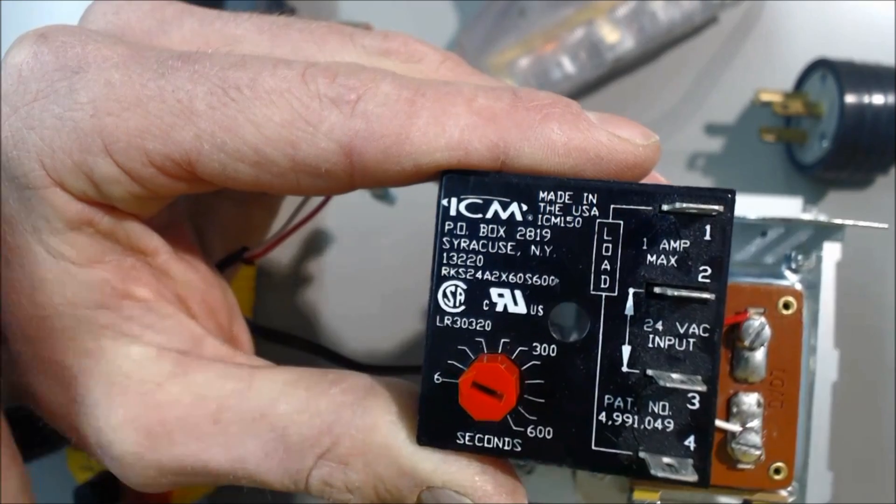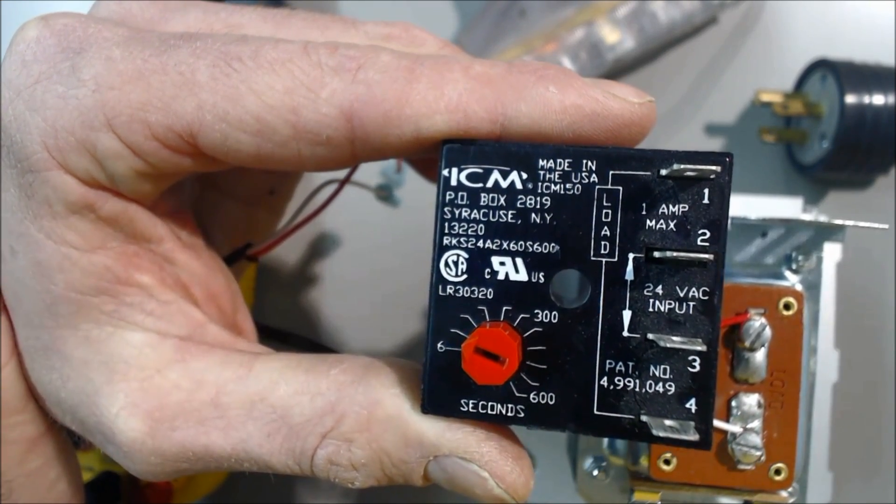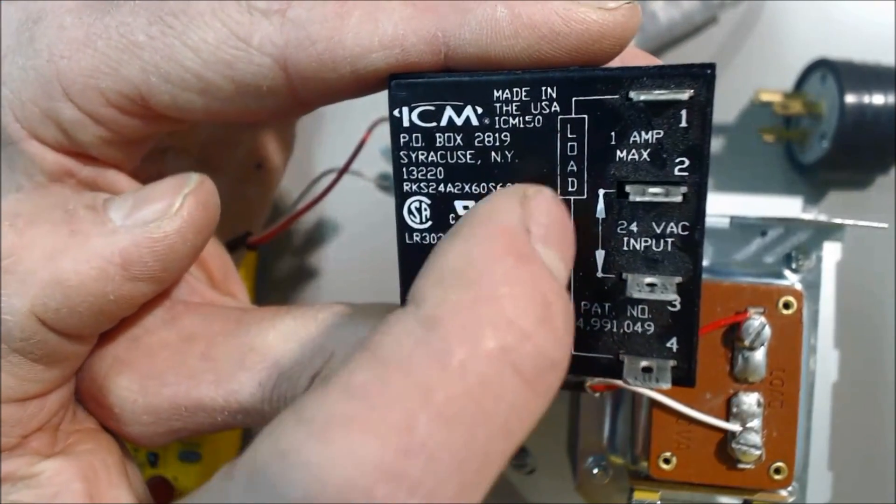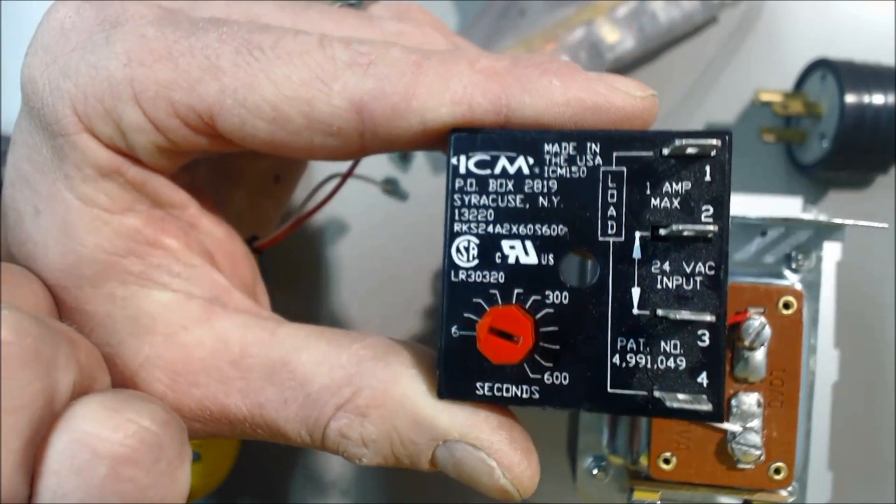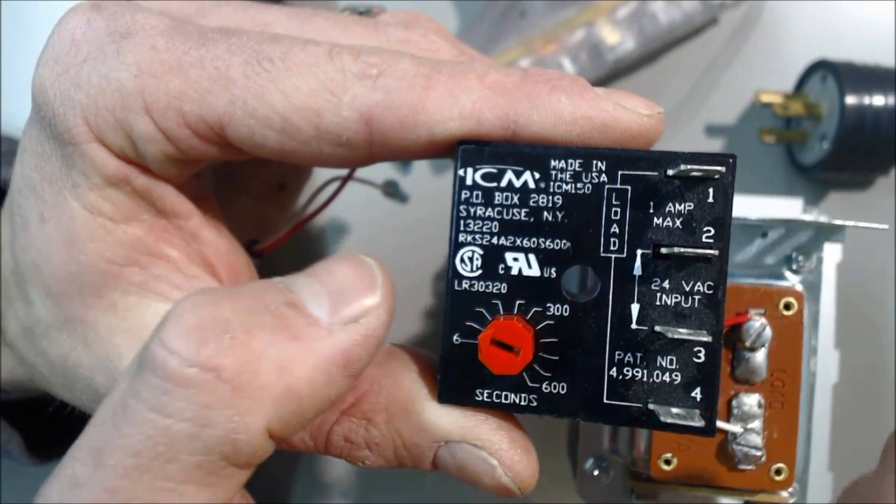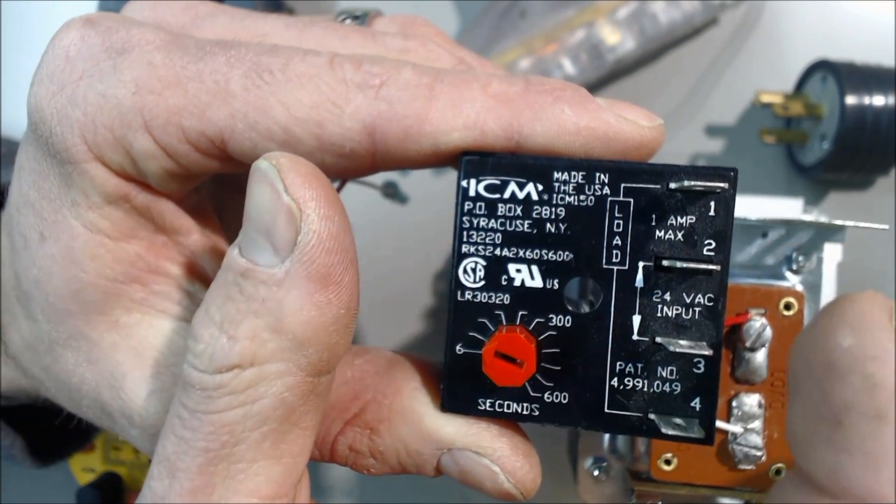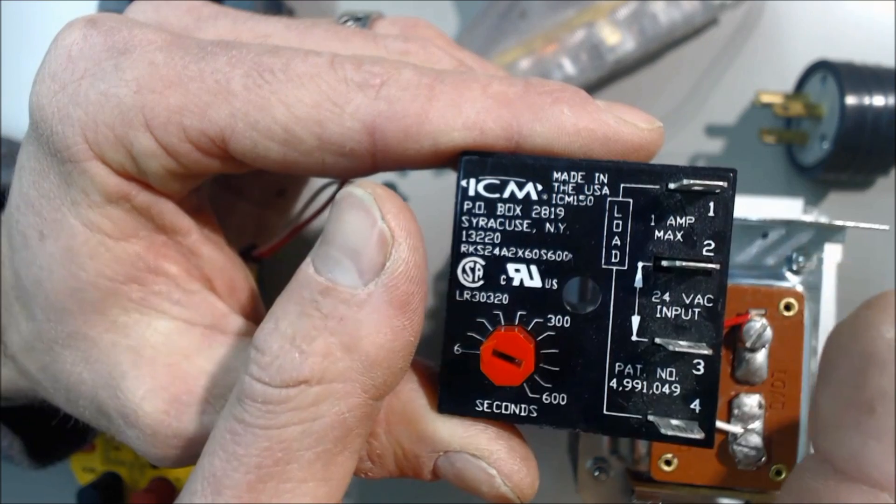This would normally be used for outdoor condensing units in the electrical compartment. You would just put a screw through here into the shroud inside the compartment, and you would take your 24 volts coming in.